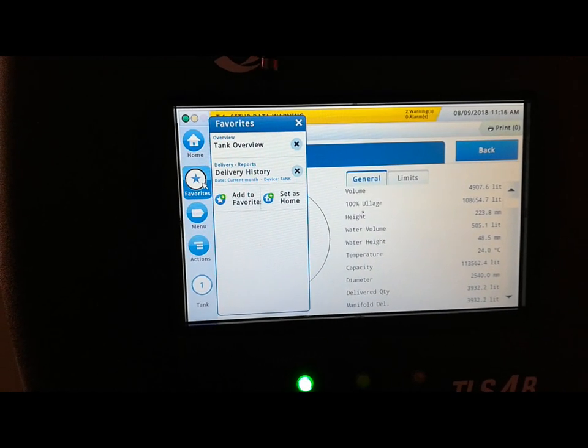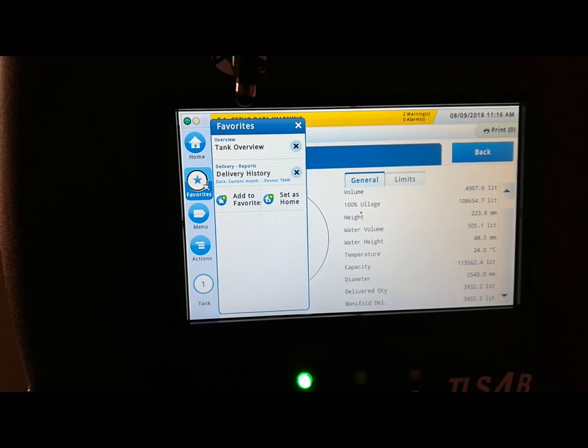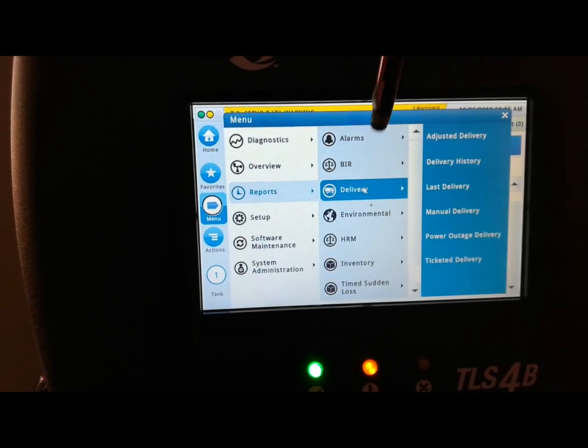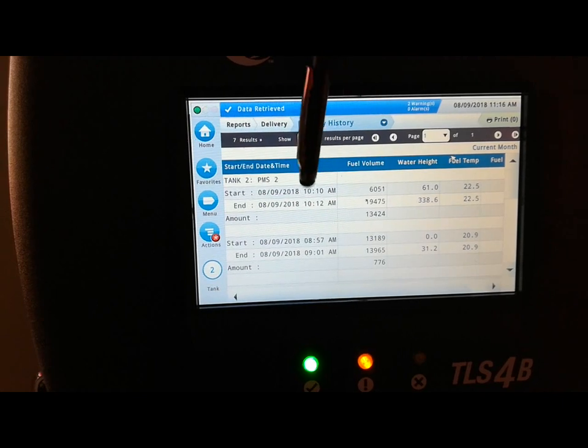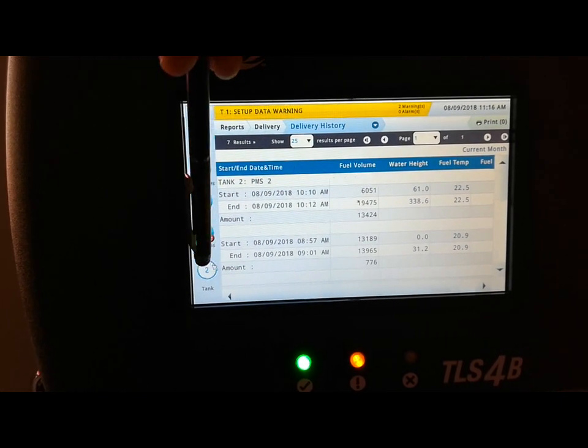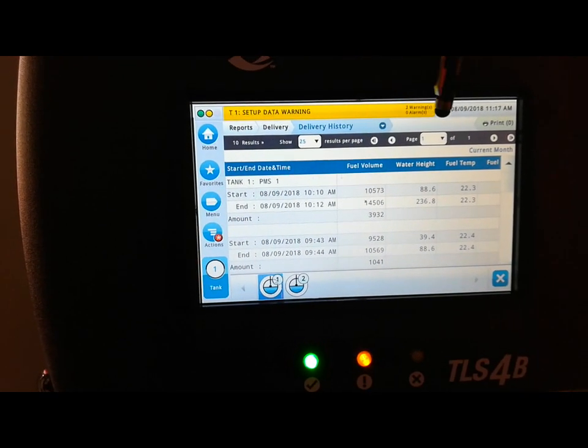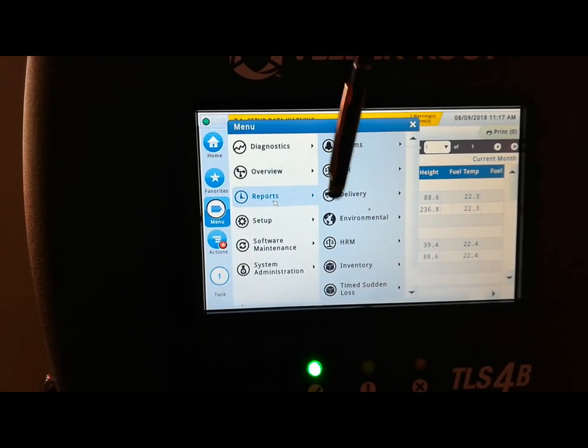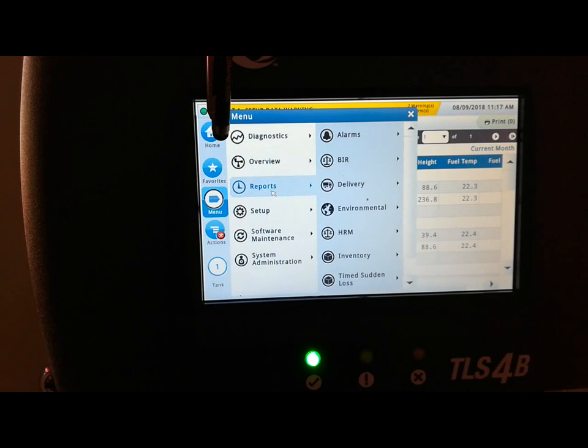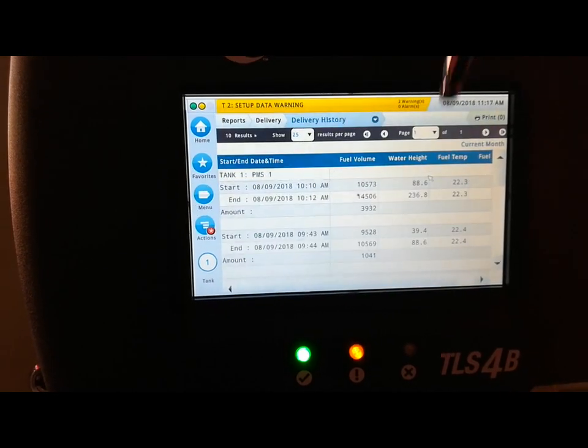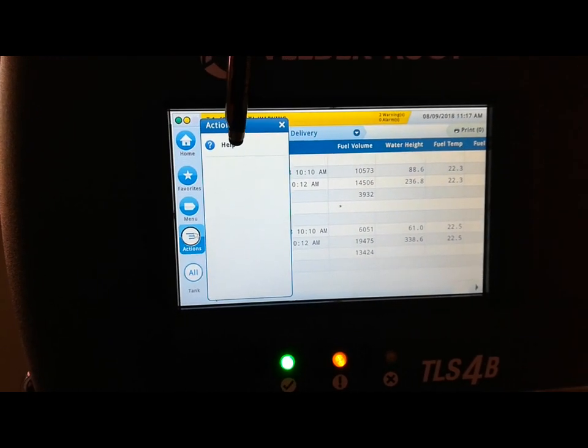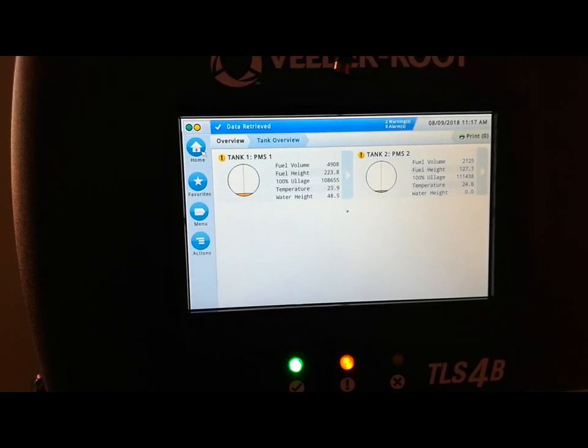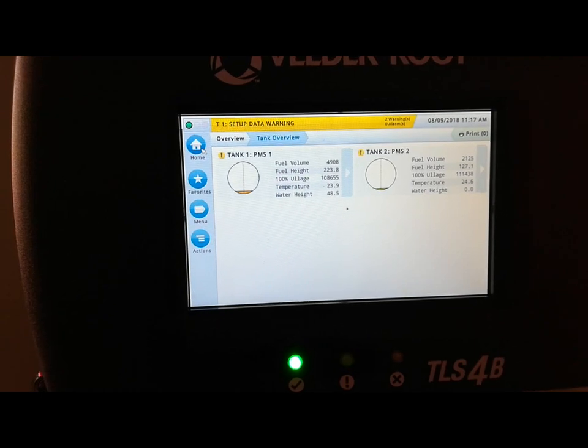You have a favorites button here — in favorites you can store anything you want for quick access without going through the menu bar. From the menu you can access various reports, for example the delivery report. Going into delivery history, you can see delivery history per tank — what was delivered, the water level at the time of delivery, and the temperature. You can also run inventory reports, environmental reports, loss reports, and alarm reports. Most interestingly, at any point if you need help on the current screen, you can go into Actions and then Help to get help on that topic.